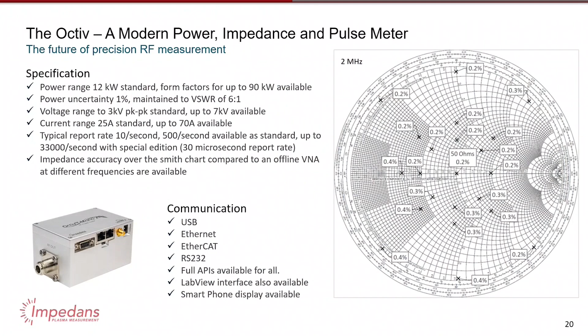Yeah, this one. So I mentioned actually with delivered power, the calorimetry is only to calibrate this probe. It is not a calorimeter. It doesn't have water on board and measuring heat or whatever. It's all done by a remote pickup. It picks up different strengths of electric and magnetic fields, and we make a database of how all that responds versus power, and versus impedance and everything else. So this makes this equivalent to a calorimeter in a way.